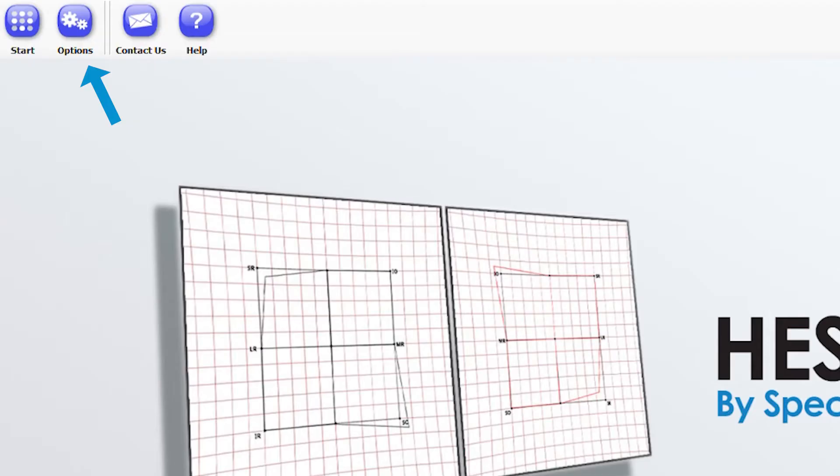It's essential that they are positioned centrally and perpendicular to the screen. The program defaults to 50 centimetres, but if you want to plot a wider field, you can position the patient closer — but then be sure to edit and save the distance from the screen in the Options menu. Also be sure that the patient's head position is correct. It must not be tilted or turned to the left or turned to the right.